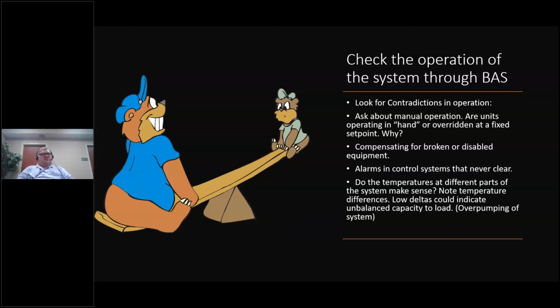But you're controlling the system based on those numbers. And so while it looks odd, it has a deeper meaning that's going to affect something else, because control systems look to those values to make decisions. If you're in automatic, it's going to look at it and think, well, okay, I need to control to this, but is that right? Is that accurate? Low deltas indicate an unbalanced capacity to load. You're overpumping the system. But again, it looks at a contradiction: I'm not getting the water to where I need to get it. That's all an issue that you're going to have to look into to resolve.